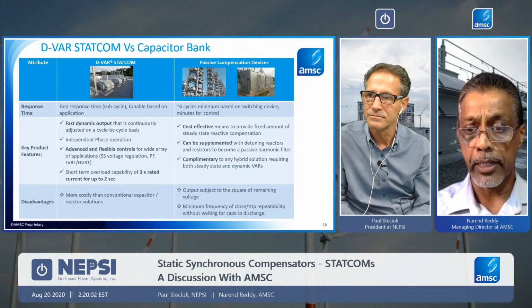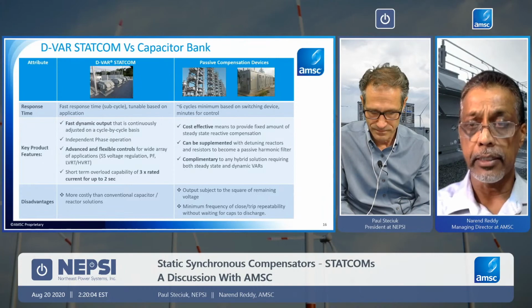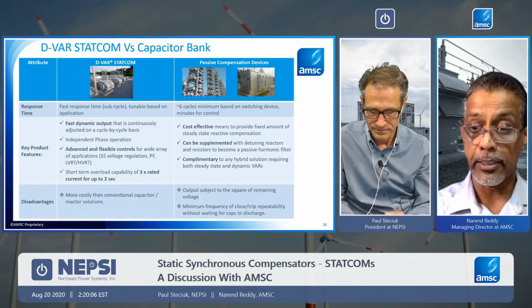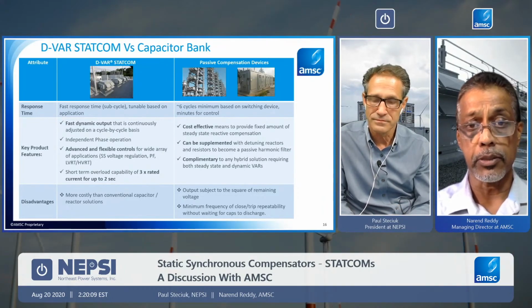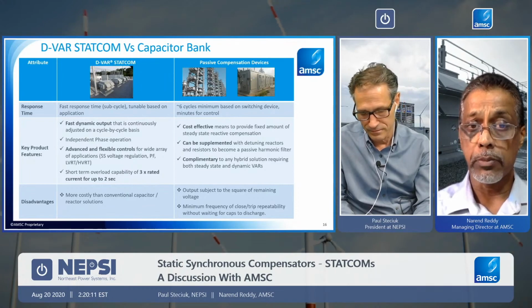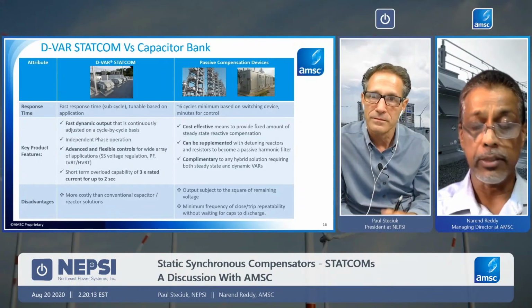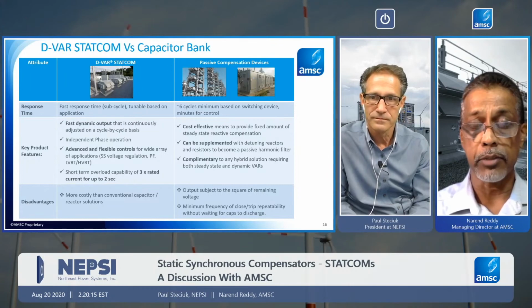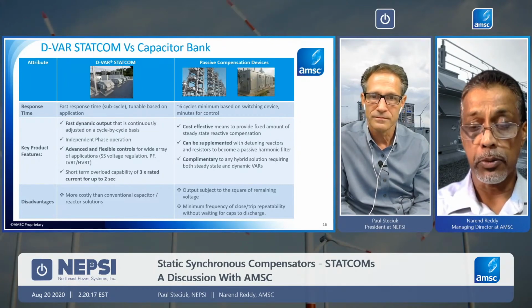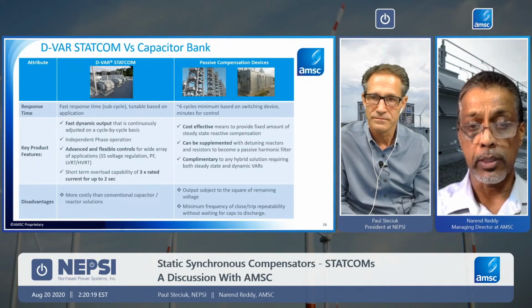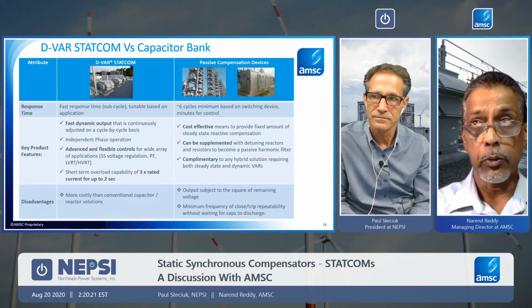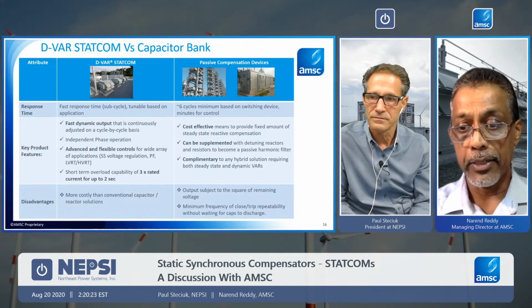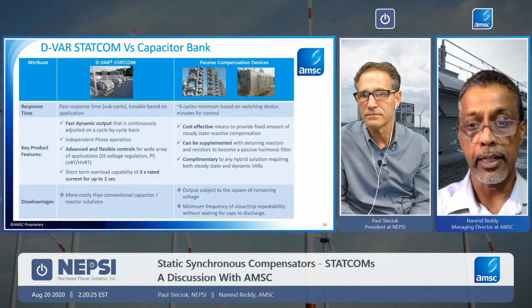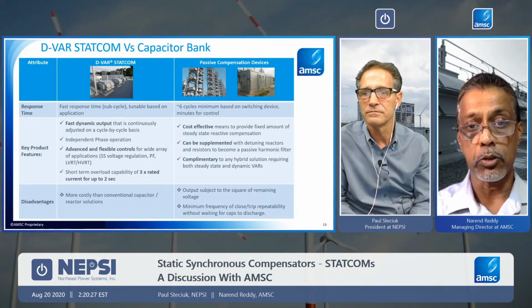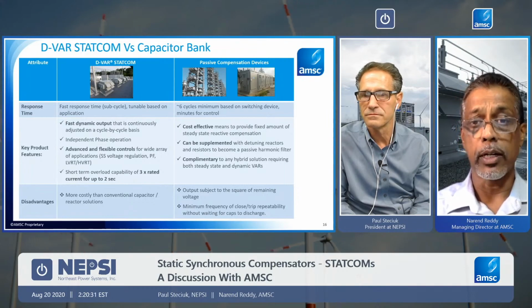The primary thing is that the STATCOM is a dynamic device and it's very fast. In other words, it has a sub-cycle response time, and it's tunable based on application. Based on our experience, sometimes you need the full output of a system, maybe 20, 30, 40 megavars, anywhere from a 30 to 50 millisecond time frame to maybe a second. It really comes down to the application and what the system requirements are.